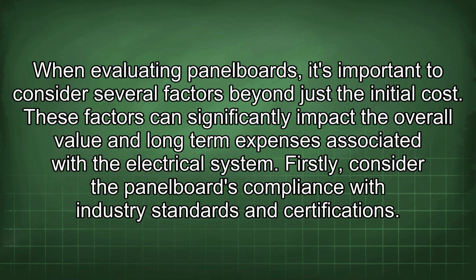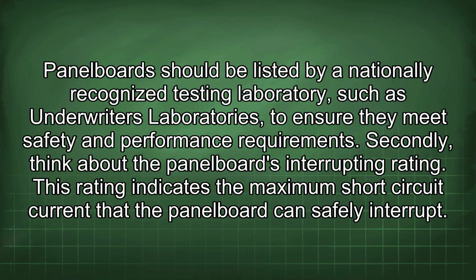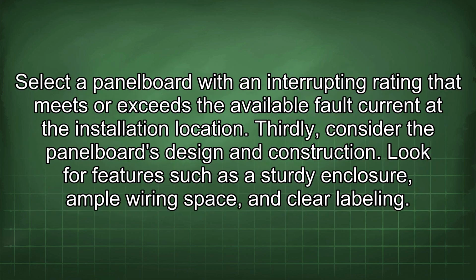Firstly, consider the panel board's compliance with industry standards and certification. Panel boards should be listed by a nationally recognized testing laboratory such as Underwriters Laboratories to ensure they meet safety and performance requirements. Secondly, think about the panel board's interrupting rating. This rating indicates the maximum short-circuit current that the panel board can safely interrupt. Select a panel board with an interrupting rating that meets or exceeds the available fault current at the installation location.